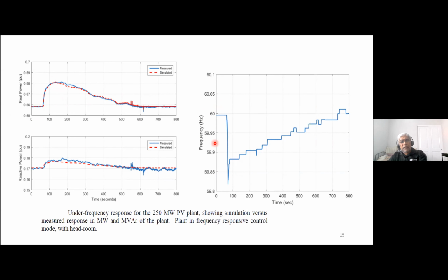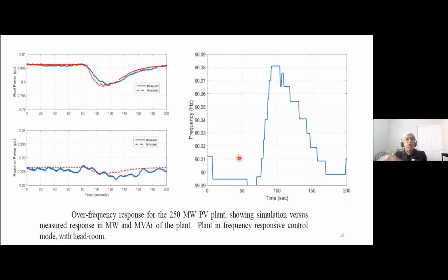So this is one case, and this is an over frequency case, and here you notice the active power actually drops. So you notice the close resemblance of the measured response with the simulated response, and that is how they verified the efficacy of this particular model.